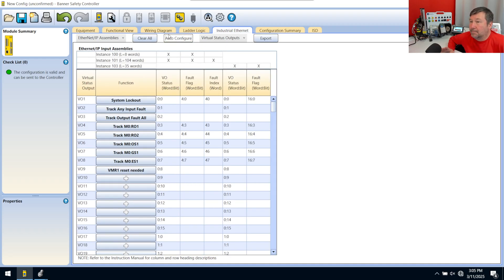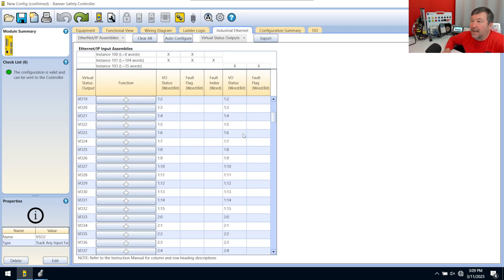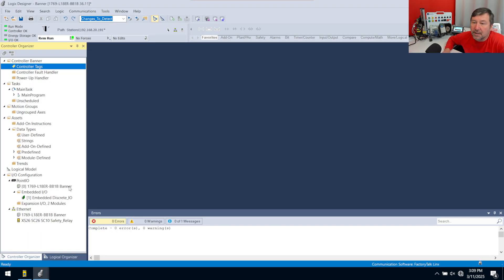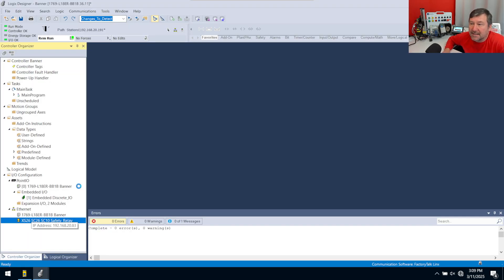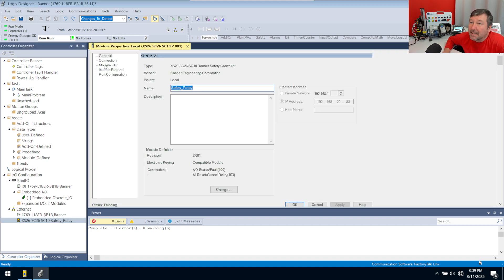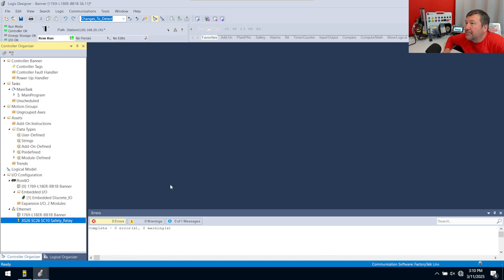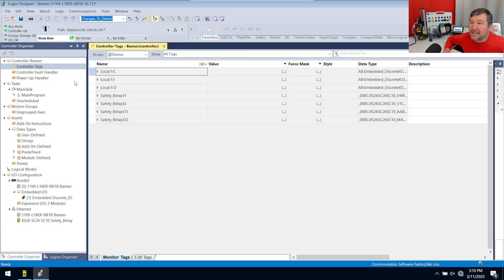Then hit the Auto Configure button and we're done. All of the mapping will be shown here — instances 100, 101, and 103 correlate to the instances we just mapped in the Banner safety software. We have our status fault on instance 100 and our reset cancel delay on instance 103. Let's open up our controller tags and see what we can see.